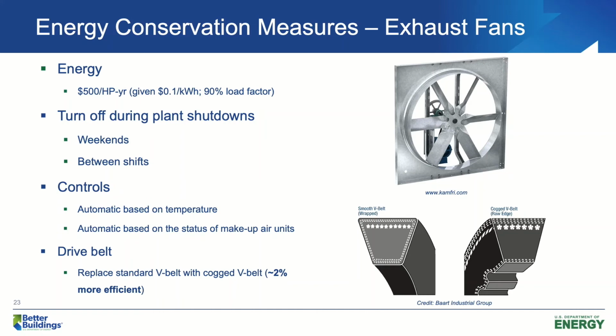If your exhaust fans are driven by standard V-belts, you can change them to cogged V-belts. Typically, cogged V-belts can give us more energy efficiency. So that is the energy conservation measures for airside equipment, air handling units, makeup air units, and exhaust fans. Now, let's talk about the water side equipment.